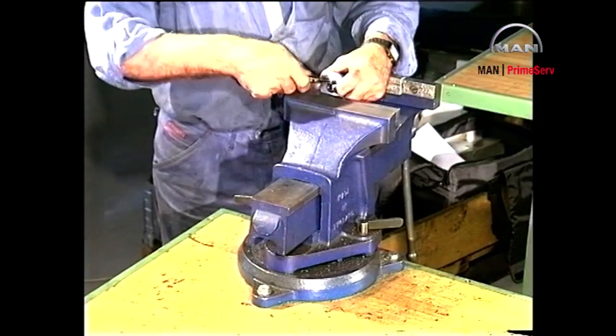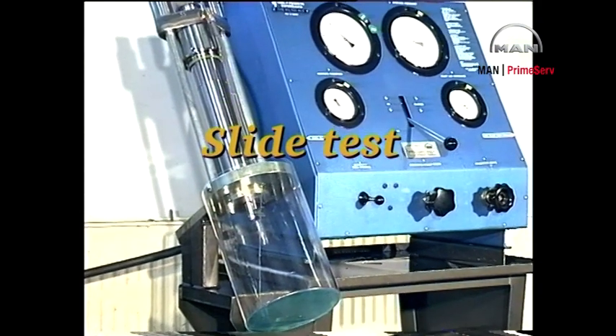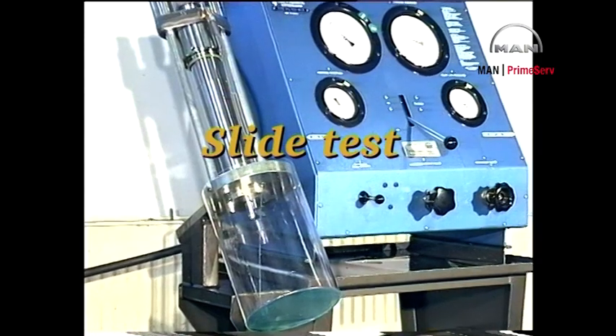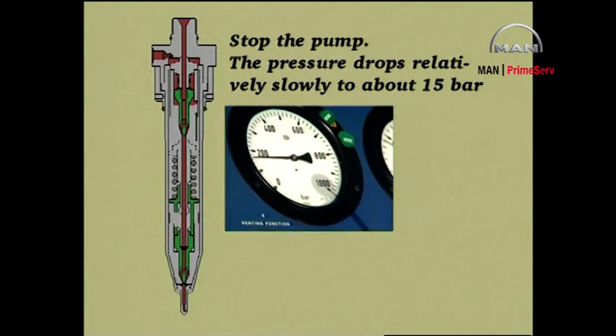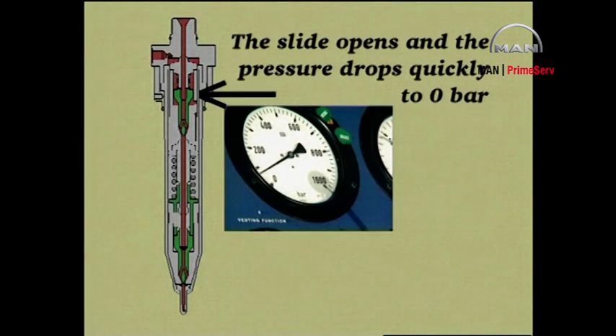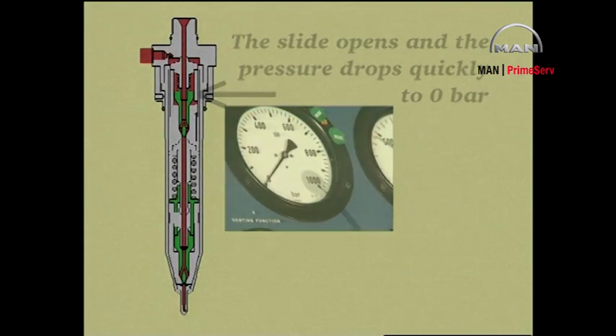The fuel valve must be re-tested after any adjustment. If the quick pressure drop cannot be registered, the slide is sticking or the hole is blocked. Disassemble and examine the parts, replace if necessary.